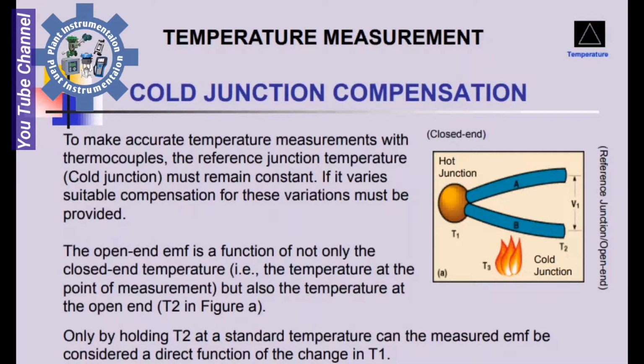Cold junction compensation: to make accurate temperature measurements with a thermocouple, the reference junction (cold junction) temperature must remain constant. If it varies, suitable compensation for these variations must be provided. The open end EMF is a function of not only the closed end temperature, the temperature at the point of measurement, but also the temperature at the open end. By holding T2 at a standard temperature, the measured EMF can be considered a direct function of the change in T1.